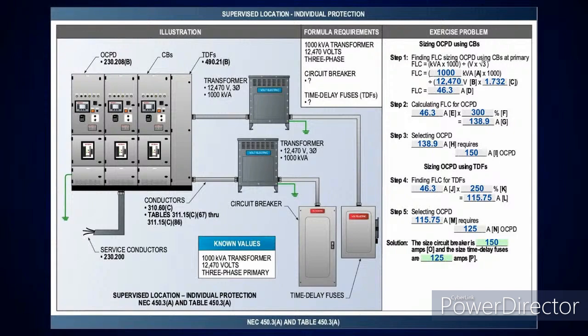One of the things I want to point out is that when you look at that, you're going to see a superscript right beside it that has a number 1. That note 1 comes down, and they're basically telling you it shall be permitted. So here I could go down or go up, but in this case, most testing is going to have you go up to the next standard size. If I take 46.3 amps at 300%, that gives me 138.9 amps, and then if I go look at table 240.6(A), that's going to give you 150 amps.